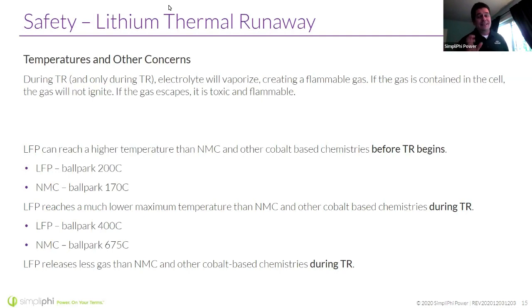Further, when LFP does reach thermal runaway, it has a much lower maximum temperature than NMC. So if thermal runaway starts, the cell is going to go through an energy expansion, essentially, and we'll see that in the next slide. But then it kind of tops out at, say, about 400 degrees Celsius, where an NMC battery may top out much higher, about 675 degrees Celsius. So it starts at a higher temperature and ends at a lower temperature. Those are good things. If the thermal runaway event is unavoidable, these things lend to a safer battery chemistry.